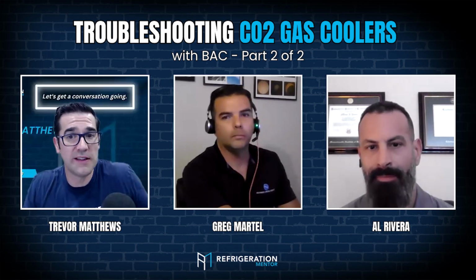I know this is a big issue. I've seen people send me videos, and it goes down a quarter of the pad and then it's dropping right off onto the ground. Like it's kind of flying off the pad, not absorbing into the pad. And that is actually an issue, right? Because we want to wet the pad as best as possible. And if we don't, then we're losing capacity. We're not doing this job. We're losing efficiency. Yeah. So I'm having a hard time.